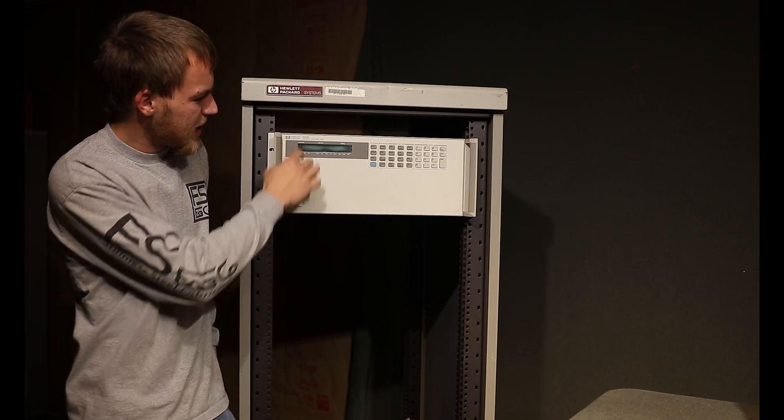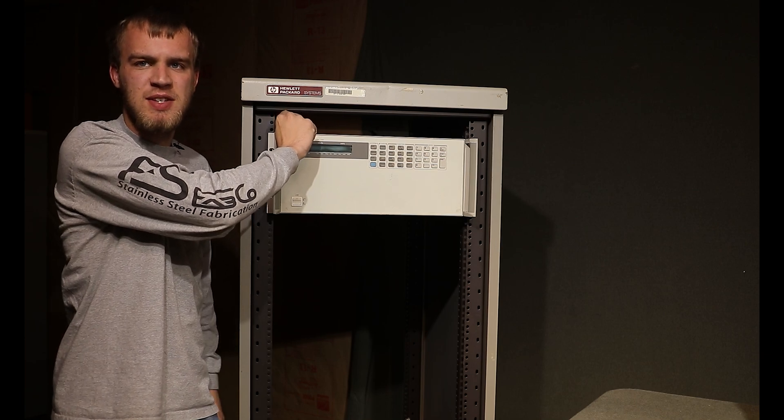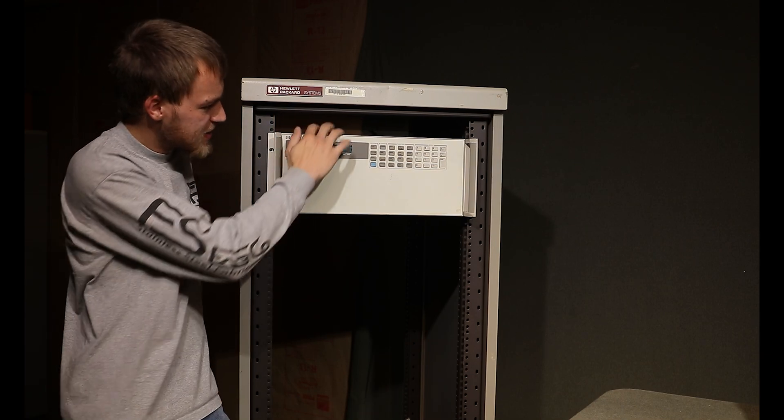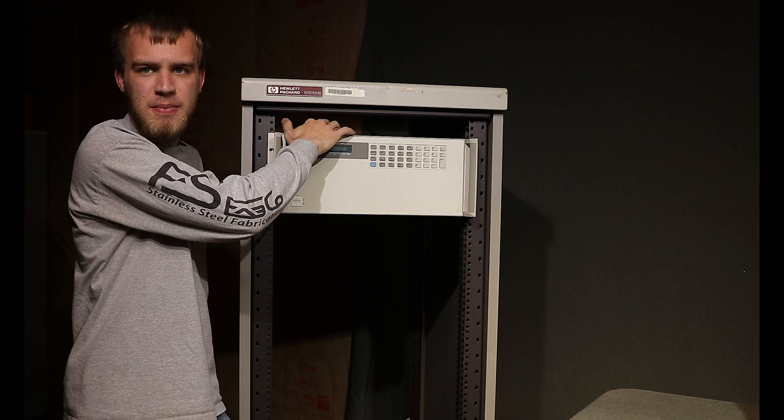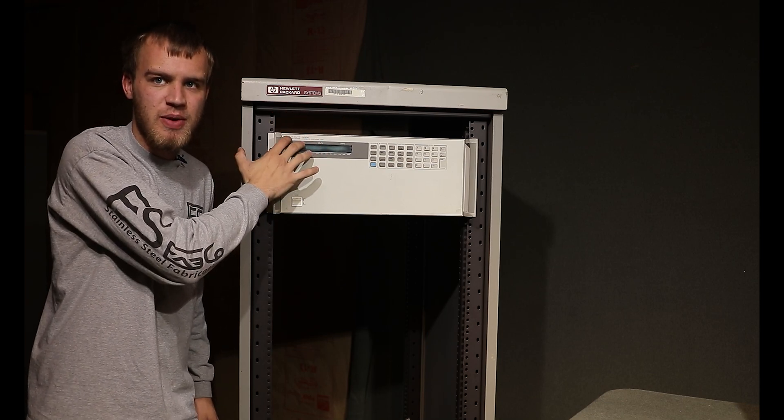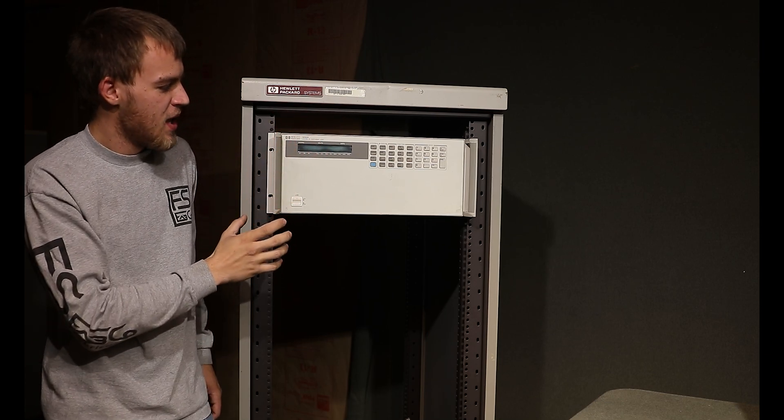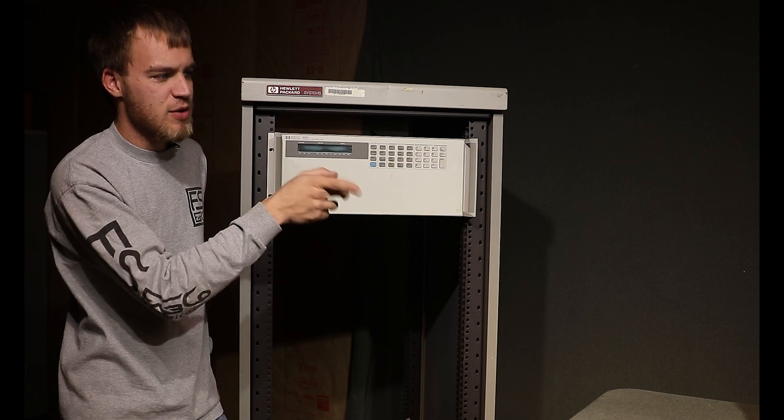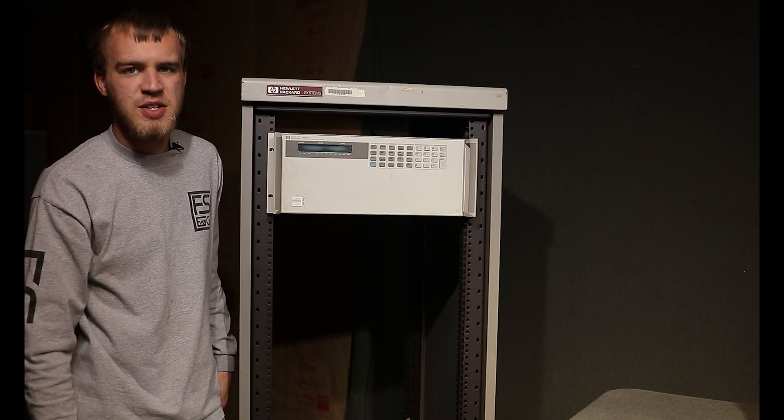And there we go. Now I made sure I left a space at the top of one U because this breathes on the top as well so we wanted to make sure we have enough airflow for this. Now I'm going to go ahead and get the power supply provisions in place.